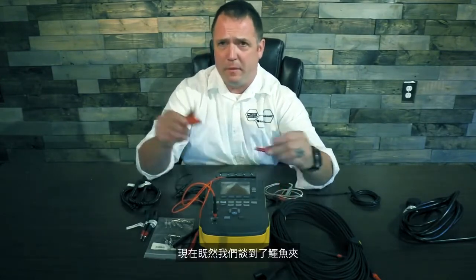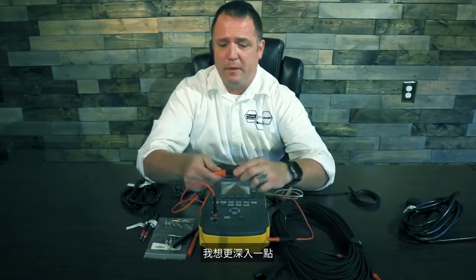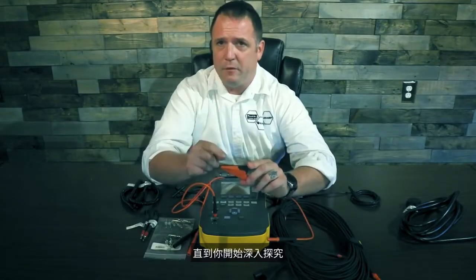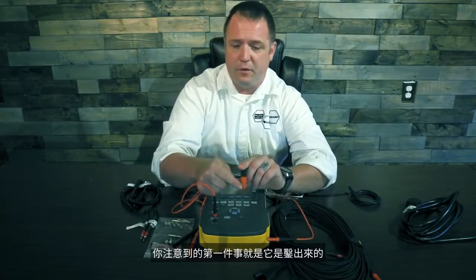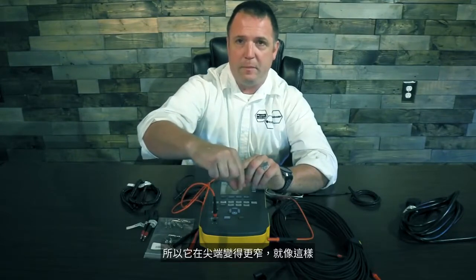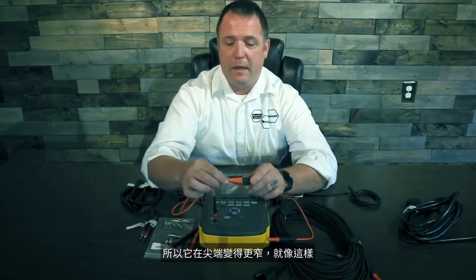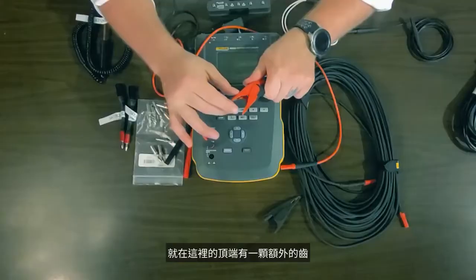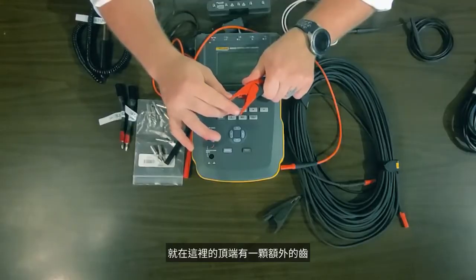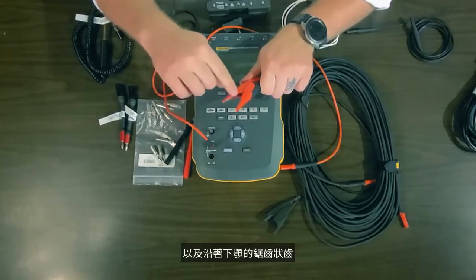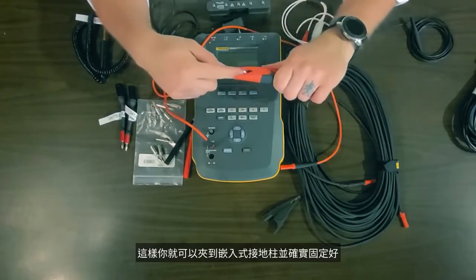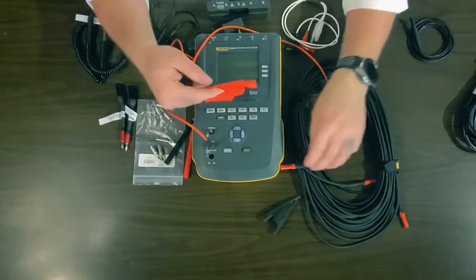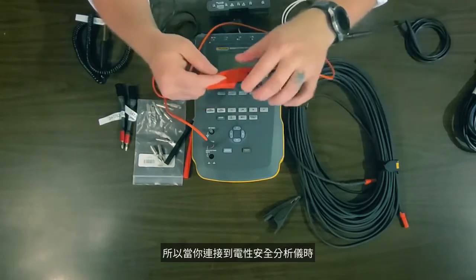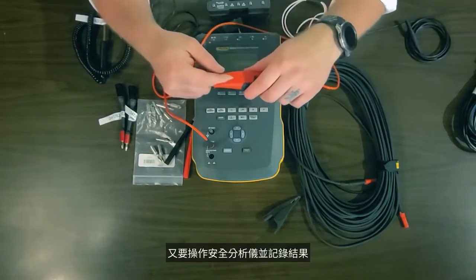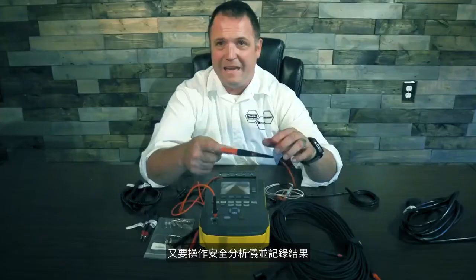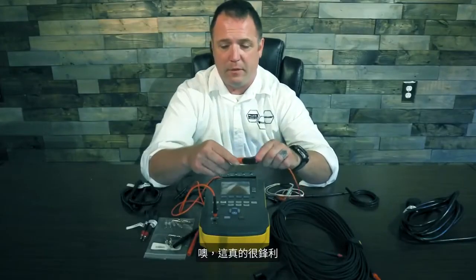Now that we talked about this alligator clip, I want to go a little bit more in depth with it. It doesn't sound like a big deal until you start digging into it. The first thing you notice is it's chiseled. So it gets narrower at the tip here, as well as this way. And then when you open it up, there is an extra tooth right here at the very tip, as well as some serrated teeth here along the jawline, which allows you to reach into those recessed ground pins and really hold on. So when you're connected to your safety analyzer, you're not trying to hold that cable on there and then record your results at the safety analyzer. It's going to hold it in place for you. Ow, is that thing sharp.